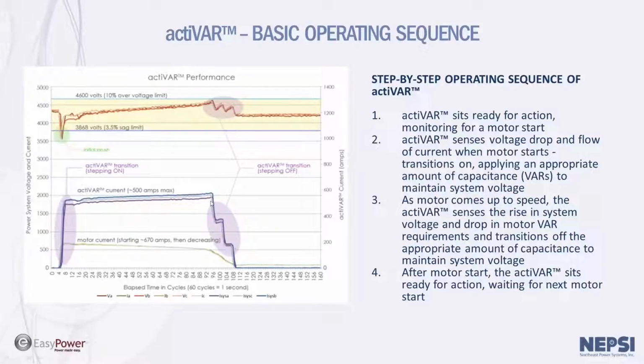You see 3 switching operations here. The first stage coming off, second stage coming off, third stage coming off. And this happens over a very short period of time. And that is one of the advantages of the actiVAR when you consider it in comparison to a conventionally switched capacitor start bank. Conventionally switched cap banks use breakers or switches. These are much slower in operation. And this period of time where the reactive power requirements for the motor are dropping off is a very short period of time, and it's very typical that during this off period of time, as the motor reactive power requirements are dropping off, a capacitive start that utilizes breakers or switches will get an overshooting voltage. Because the actiVAR can switch within one cycle, we tend to avoid that overshoot that can occur.